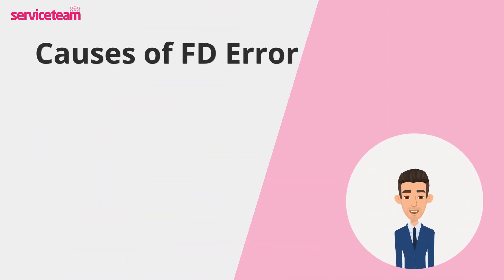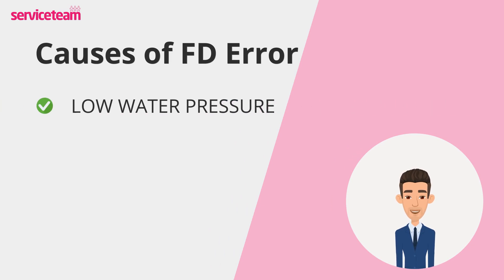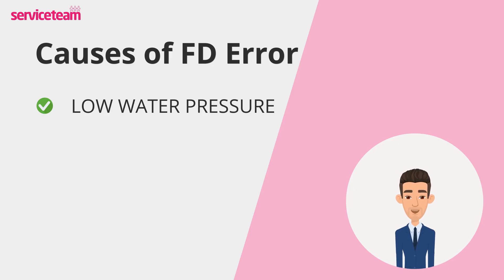Let's review the most common reasons for the FD fault on your Ideal Boiler. The first cause is low water pressure. Your boiler needs a steady pressure to run smoothly, ideally around 1.3 bars. If it drops below 1, your boiler might not detect enough water flow, which can trigger the FD fault code.